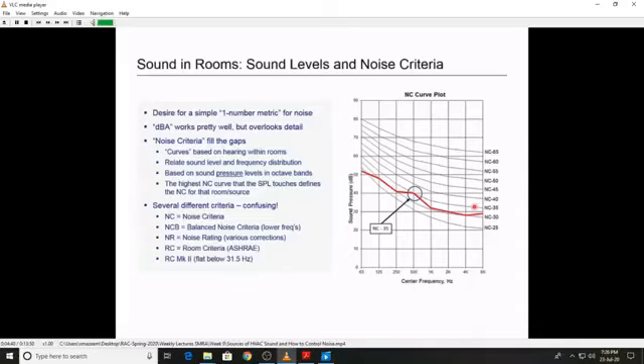Unfortunately, there are several different noise criteria: noise criteria, balanced noise criteria, noise rating, room criteria Mark II. These have all shown up in various requirements for HVAC systems. The most common two are noise criteria, the NC curves, and the room criteria, which ASHRAE has recommended in the past. One important thing to note is that you cannot plan as an equipment manufacturer for a specific noise control rating. The only thing you have control over is the sound power and the shape of the spectrum from your equipment, because in the end the noise criteria depends on the room itself, the size of the room, and the amount of acoustical absorption in the room.